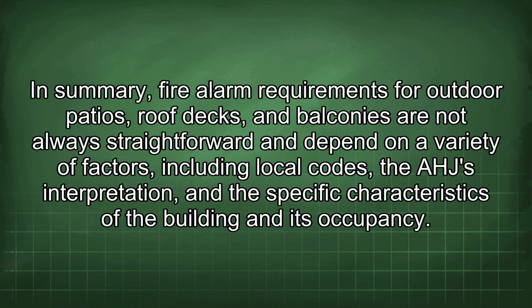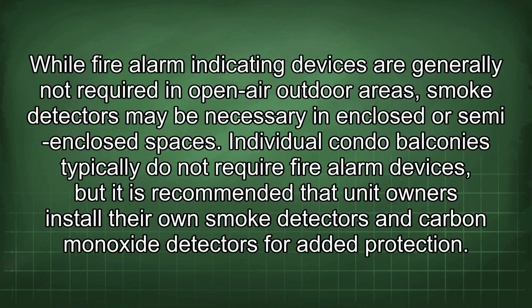In summary, fire alarm requirements for outdoor patios, roof decks, and balconies are not always straightforward and depend on a variety of factors, including local codes, the AHJ interpretation, and the specific characteristics of the building and its occupancy. While fire alarm indicating devices are generally not required in open-air outdoor areas, smoke detectors may be necessary in enclosed or semi-enclosed spaces. Individual condo balconies typically do not require fire alarm devices, but it is recommended that unit owners install their own smoke detectors and carbon monoxide detectors for added protection.